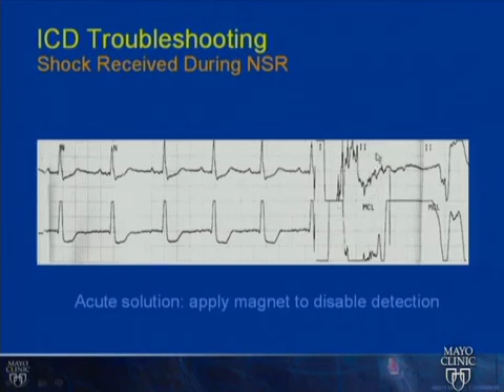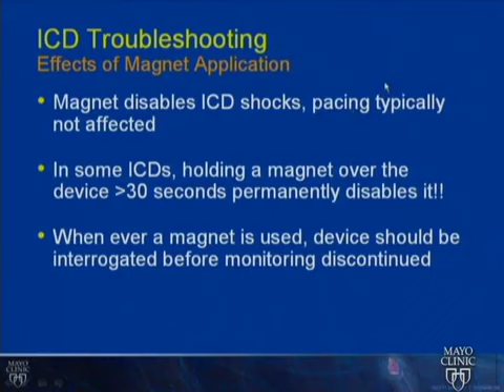And finally, if we're not sure why the device is discharging, and in this particular setting it seems on the surface lead that the patient was in sinus rhythm but received a discharge, then a magnet over the generator will disable the ICD shocks. In a patient who is pacemaker dependent, the device would usually revert to a nominal mode, but pacing would continue. In some ICDs we have to watch if the magnet is held more than 30 seconds, as it may permanently disable the ICD functions. But that particular scenario has pretty much been eliminated in the more recent devices, and once the purpose of the magnet use is completed, one must interrogate the device.